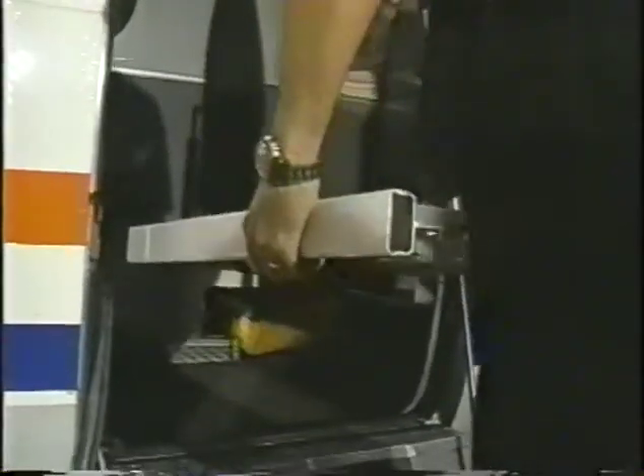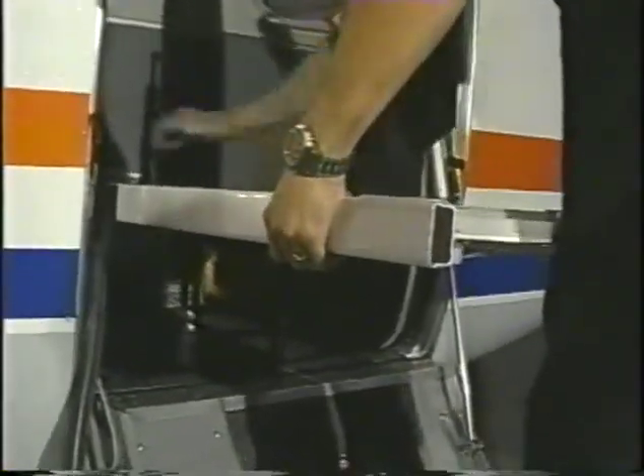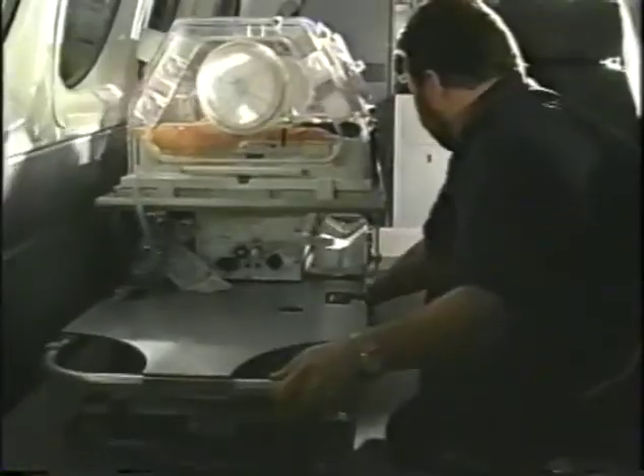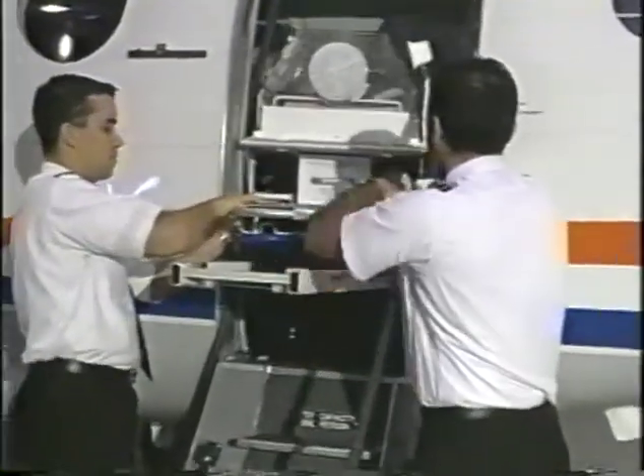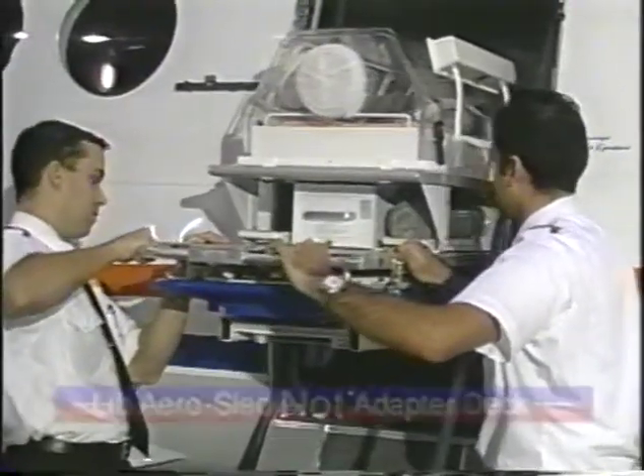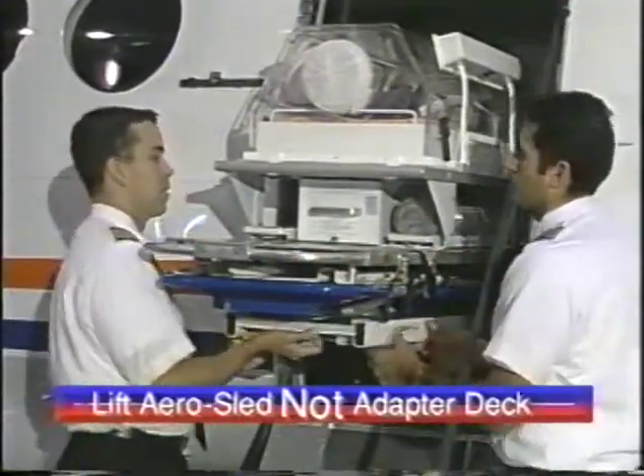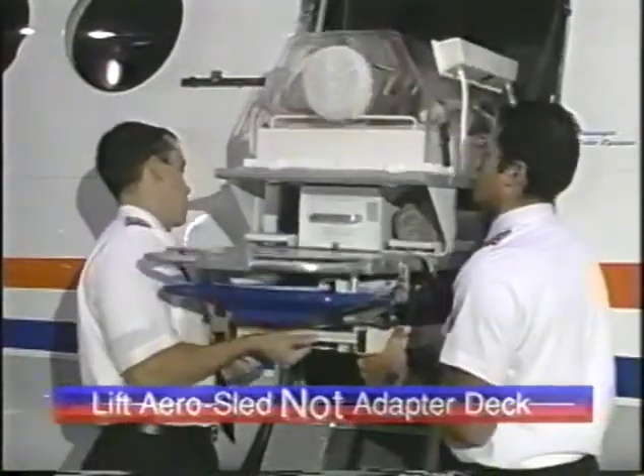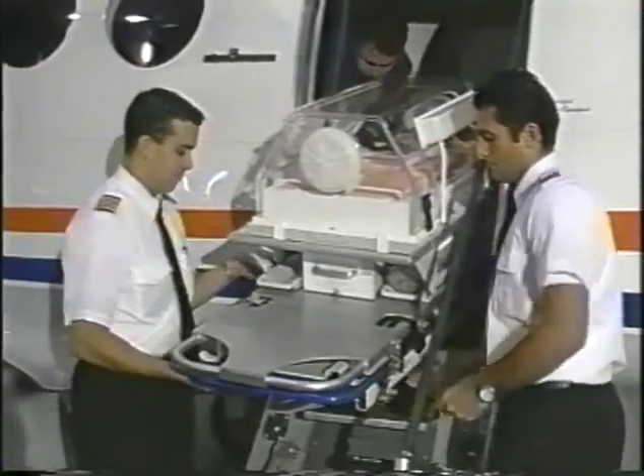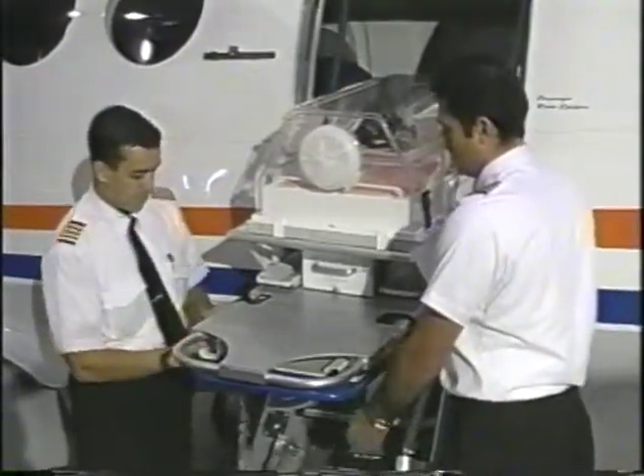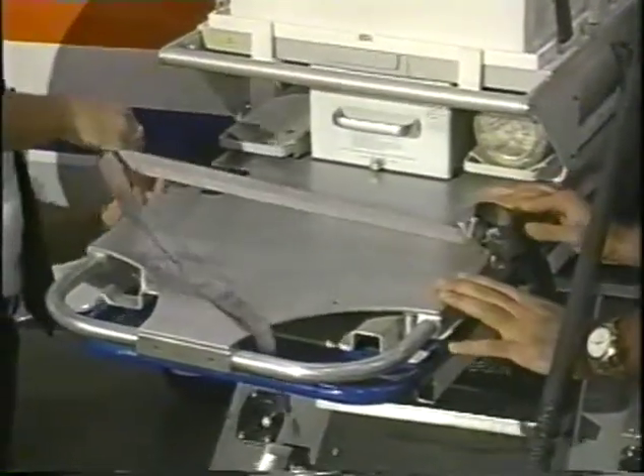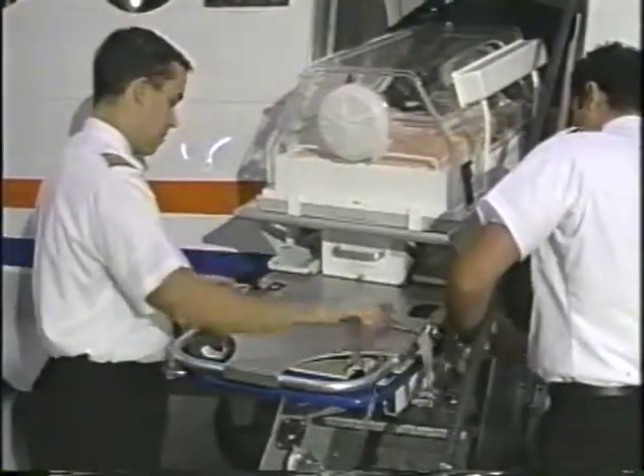The flight crew members will remove the loading ramp from the aircraft storage compartment. Connect the loading ramp to the aerosled base, leaving it in the horizontal position. Slide the adapter deck and stretcher slider onto the loading ramp protruding through the aircraft doorway, ensuring that no loose straps hang over the side of the stretcher slider. Take hold of the loading ramp and lower it to the incline position, ensuring that the flight crew members take hold of the loading ramp and not the adapter deck. Secure the strap on top of the adapter deck and remove the supplemental restraint strap from under the stretcher slider. Disconnect the two foot-end restraint straps while the air ambulance medical crew member inside the aircraft disconnects the head-end restraint.